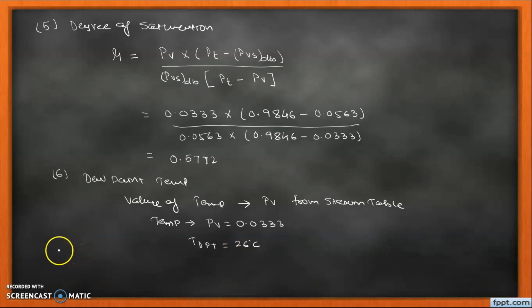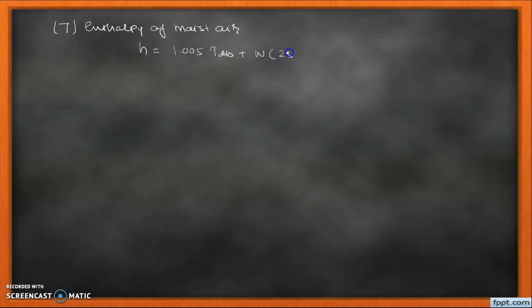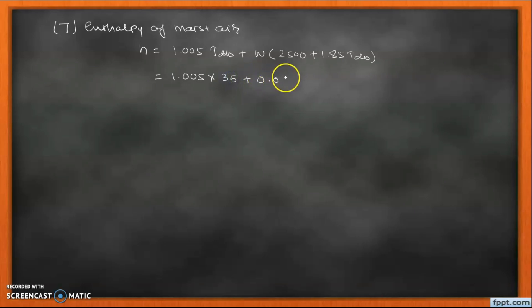Last is enthalpy. We calculate the enthalpy of moist air using the formula: h = 1.005 × Tdb + W × (2500 + 1.85 × Tdb). Substituting values: h = 1.005 × 35 + 0.0215 × (2500 + 1.85 × 35), giving the enthalpy of moist air in kJ per kg of dry air.